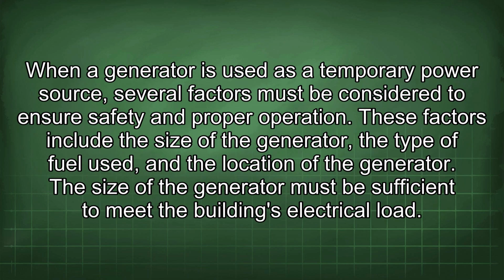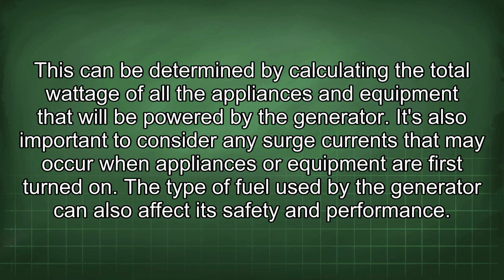When a generator is used as a temporary power source, several factors must be considered to ensure safety and proper operation. These factors include the size of the generator, the type of fuel used, and the location of the generator. The size of the generator must be sufficient to meet the building's electrical load. This can be determined by calculating the total wattage of all the appliances and equipment that will be powered by the generator.